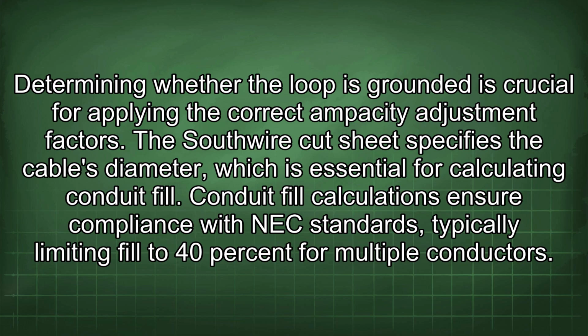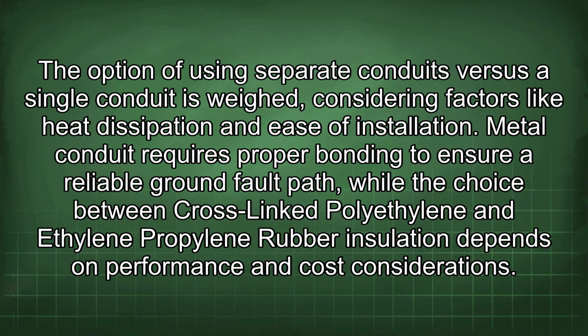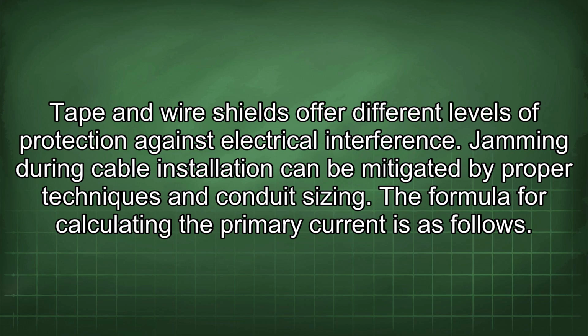Conduit fill calculations ensure compliance with NEC standards, typically limiting fill to 40% for multiple conductors. The option of using separate conduits versus a single conduit is weighed, considering factors like heat dissipation and ease of installation. Metal conduit requires proper bonding to ensure a reliable ground fault path, while the choice between cross-linked polyethylene and ethylene propylene rubber insulation depends on performance and cost considerations. Tape and wire shields offer different levels of protection against electrical interference. Jamming during cable installation can be mitigated by proper techniques and conduit sizing.